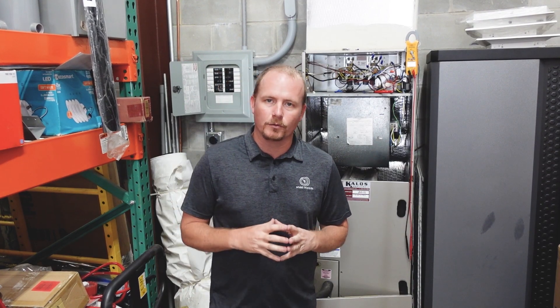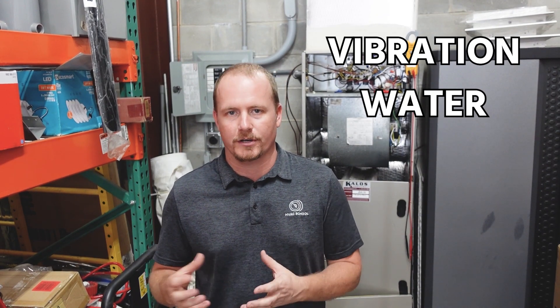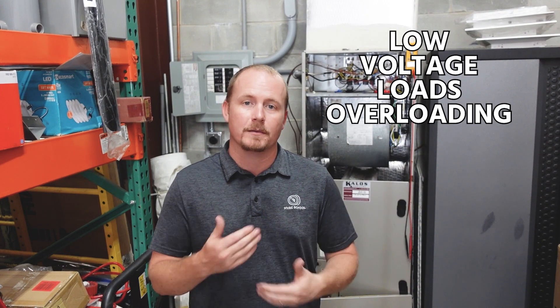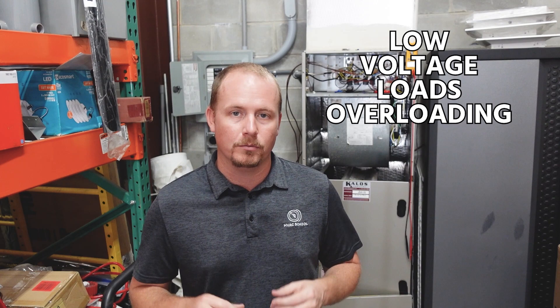Now there are situations where low voltage fuses tripping or low voltage breakers tripping can be caused by difficult to find problems. In a lot of cases that's due to vibration or water being necessary in the equation to cause the short circuit to show up. In other cases it can be because certain low voltage loads could actually be overloading, such as in cases where a contactor isn't allowed to pull fully in.